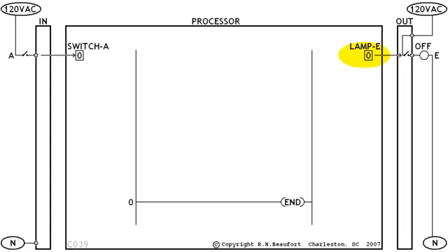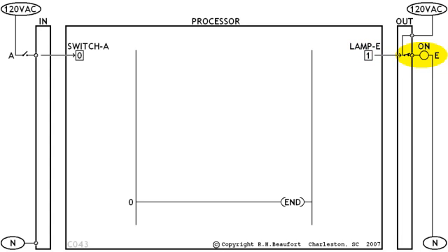Now, for the output side of things. Notice that the bit box for lamp E contains a 0 right now, and the contacts for lamp E are open, which means lamp E is off in the field. Suppose we go back to the bit box and manually change the status to a 1. Now, we'll see that the contacts for lamp E are closed, and so lamp E in the field comes on. Again, the same type of misconception. The transfer of information from the bit box to the output module is fast, but it does not happen instantly.